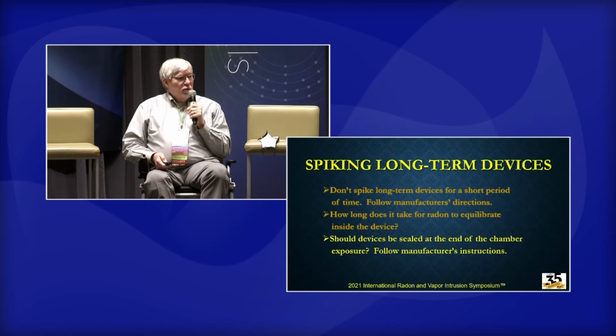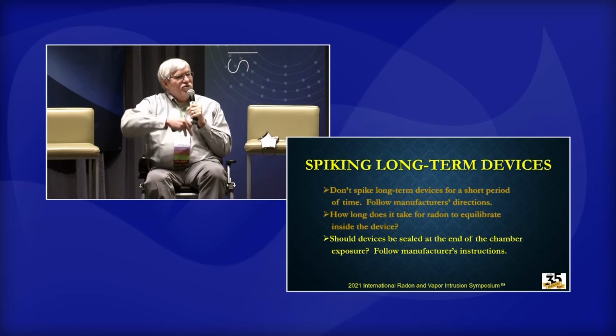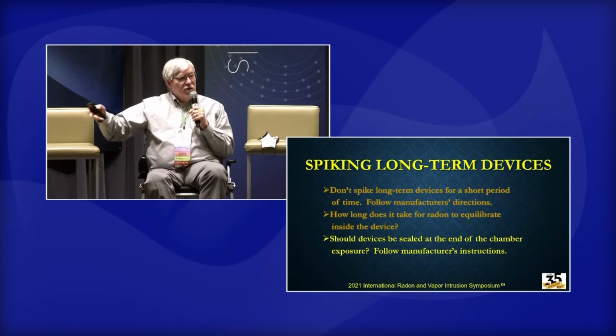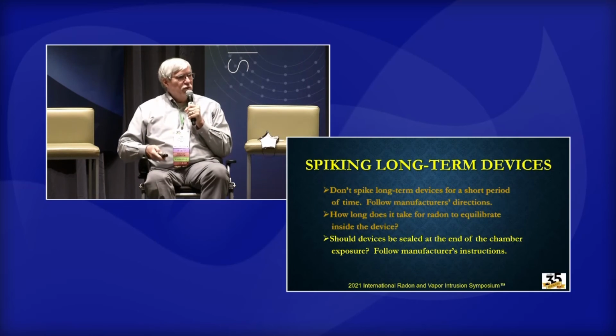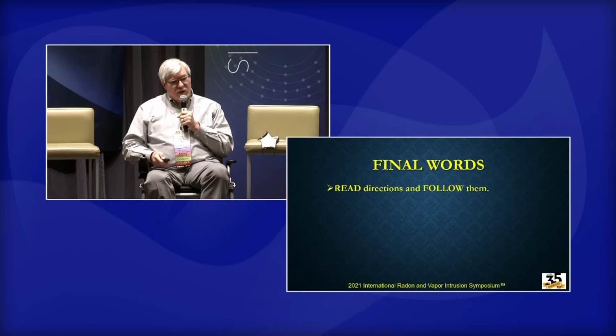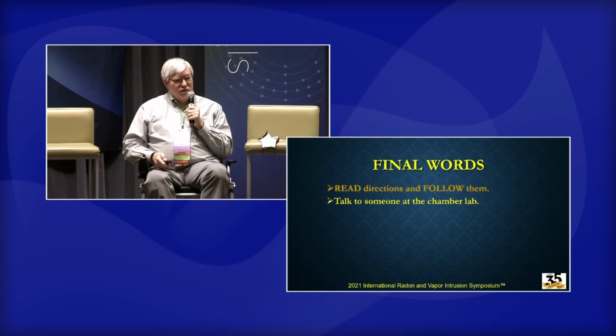They're also follow the manufacturer's instructions about whether they should be sealed at the end of the exposure or just left open. Because sometimes the radon has to then escape from the device. If you seal it up, then it can't escape, and then it continues to expose. So my final words: read the directions, follow the directions, talk to someone at the chamber.